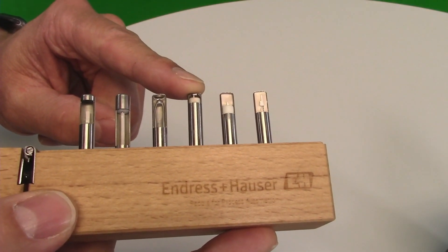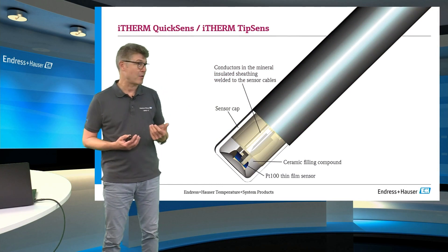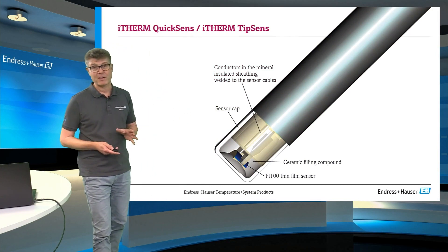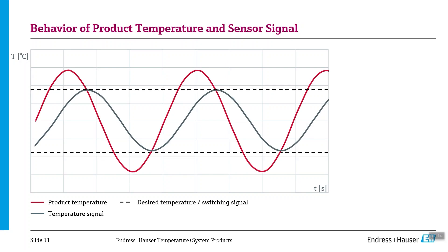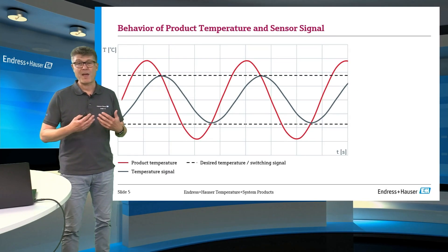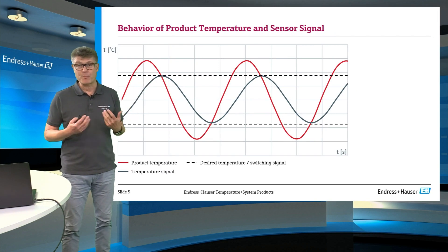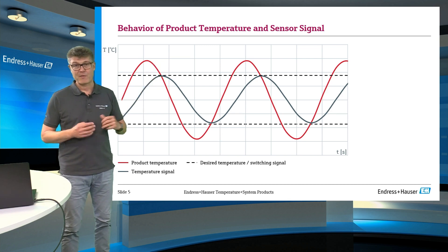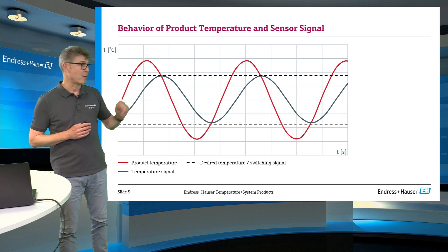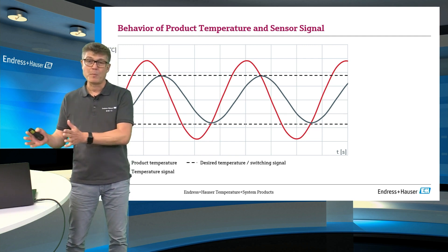It's really fixed at the metallic construction, so it is only one millimeter away from the outside. And this has big effects on safety-critical applications, as you can see in this graph. If you imagine a process which is changing up and down, a normal thermometer will have a delay, and this means it will not see the real process temperature. It will indicate a value which is not covering the peaks up and down of the real process, and it will show these maximums and minimums some seconds or minutes later.